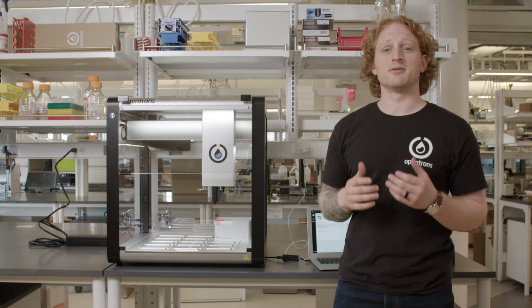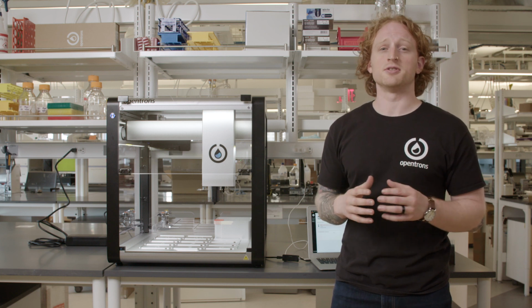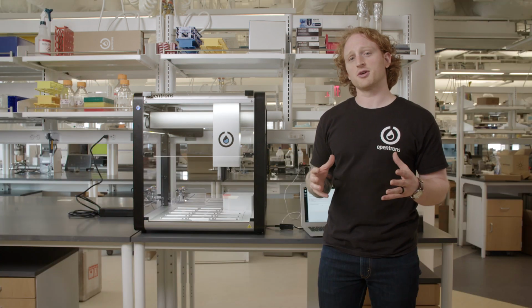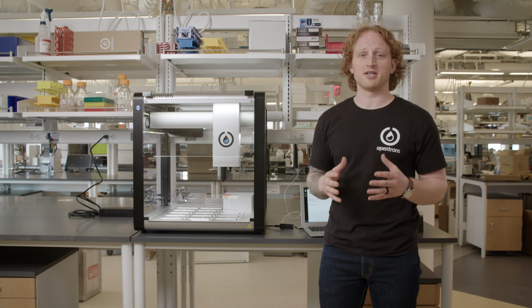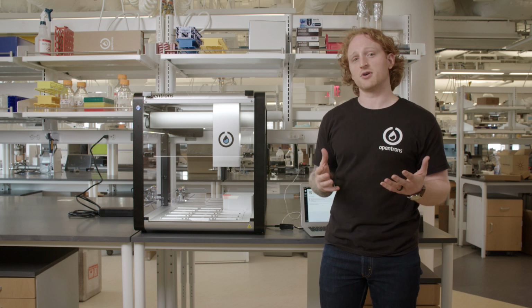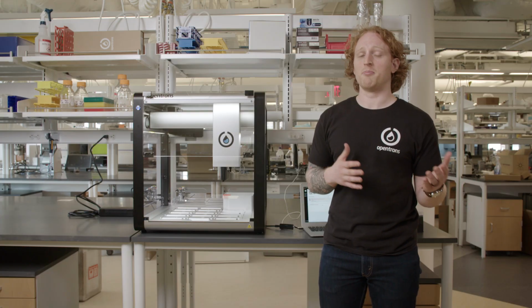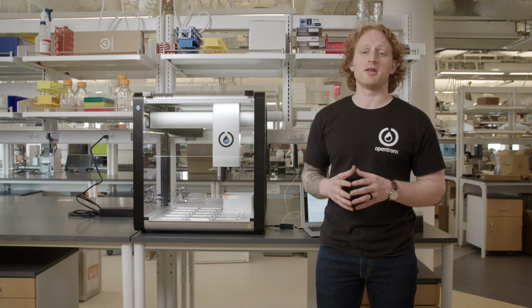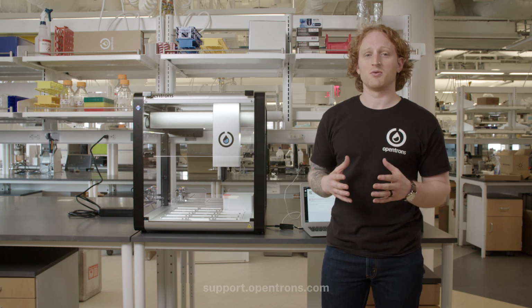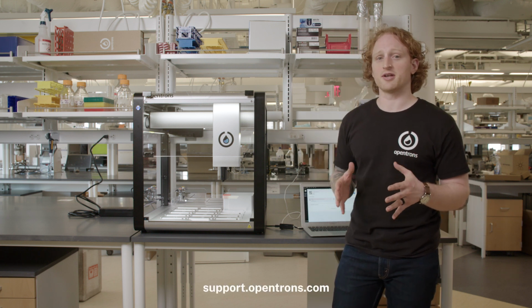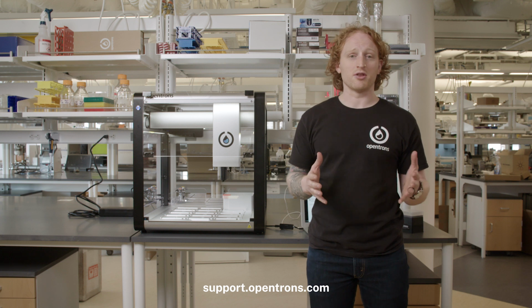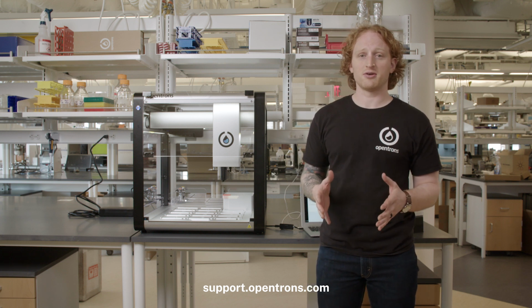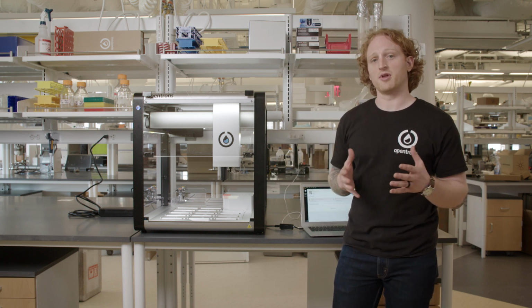Deck calibration is an important part of the OT-2's positional calibration stack. It makes sure the OT-2 moves its pipettes in the correct location and gives the OT-2 a sense of direction. A bad deck calibration can cause problems like the pipette being off position in a direction, or a mount that changes depending on where it is on the deck. We have a few articles in our help center that explain deck calibration and all other calibrations in greater detail, so you can go there if you'd like to learn more.